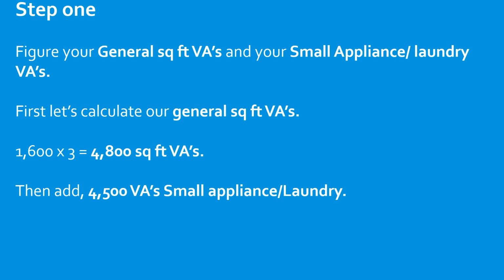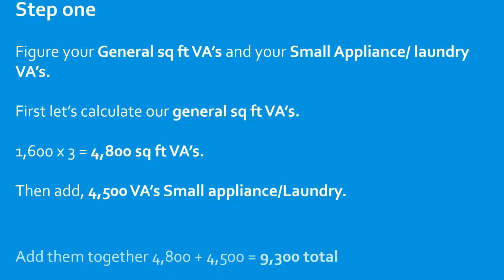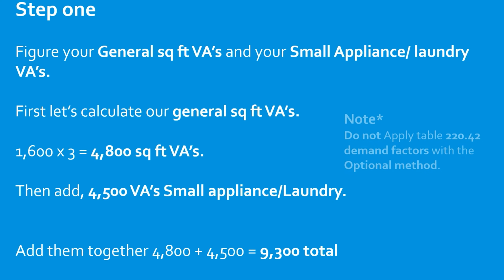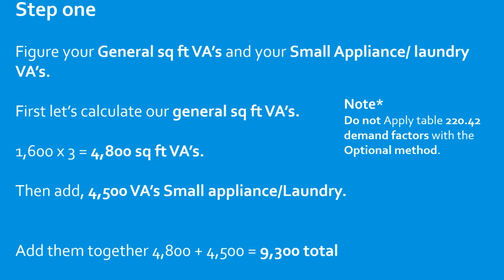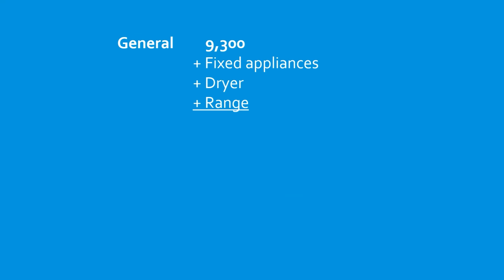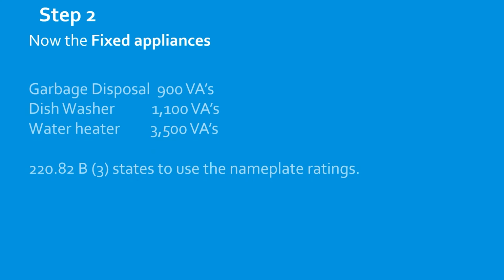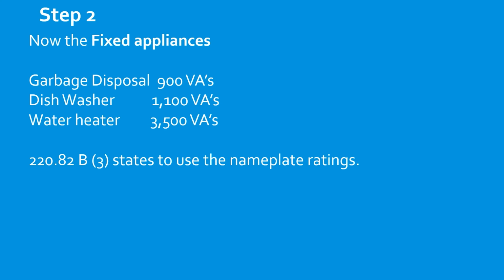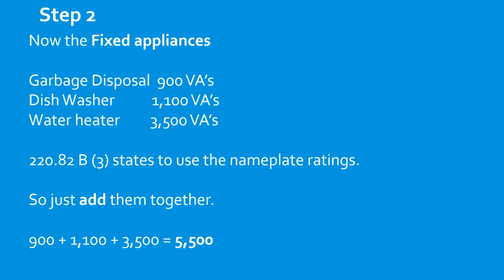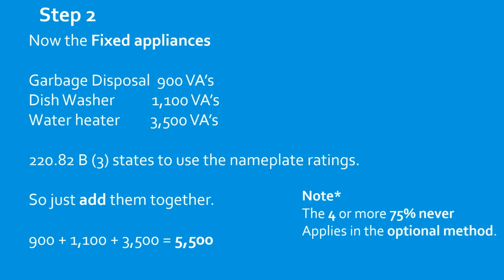These two parts of this process are the same for the optional and the standard method, except you're not going to do any demand factors for this portion until the end. Add them together, 9300 total. You do not apply the table 220.42 demand factors with the optional method. We apply one demand factor at the end. Okay, so now let's do the fixed appliances. We just total them all together. It says use the nameplate ratings in 220.82B3. Just add them together. We're going to get 5500 VAs. Note the 4 or more 75% rule never applies in the optional method.